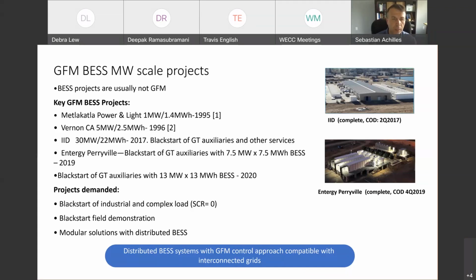The other aspect is that the solutions for this were modular, in the sense that you have small batteries and you basically add as many battery modules as you need, each with an inverter, to come up with the rating you require. Because of that distributed nature of the battery, the controls have to be compatible with having other sources close by. For that reason, the grid forming control approach that was used is compatible with interconnected grids where you may or may not have other grid forming sources or other synchronous machines in the system. That experience was very helpful.